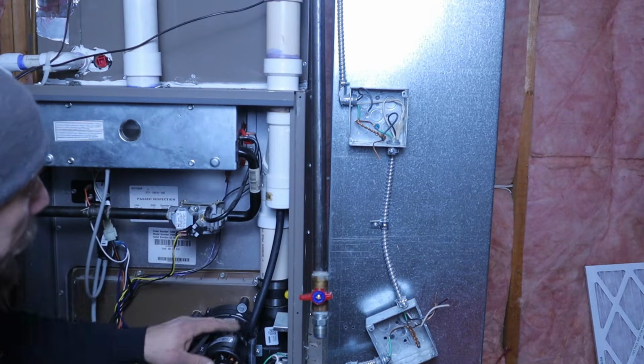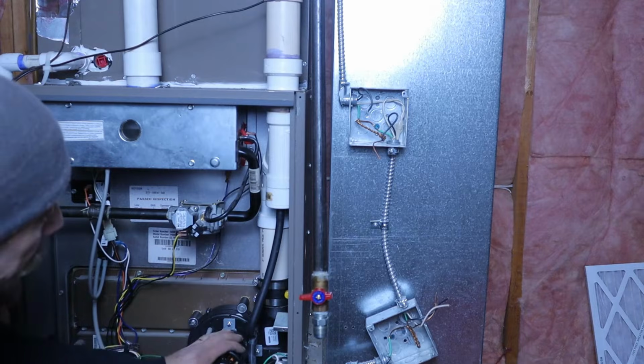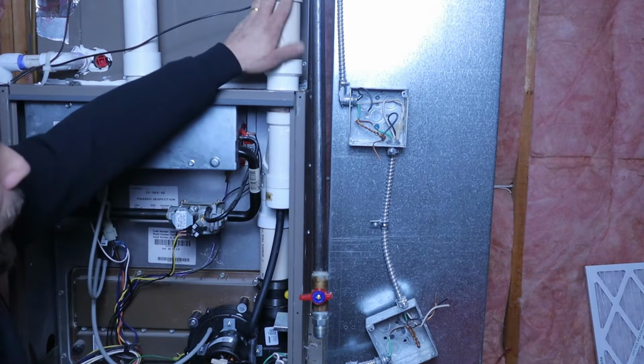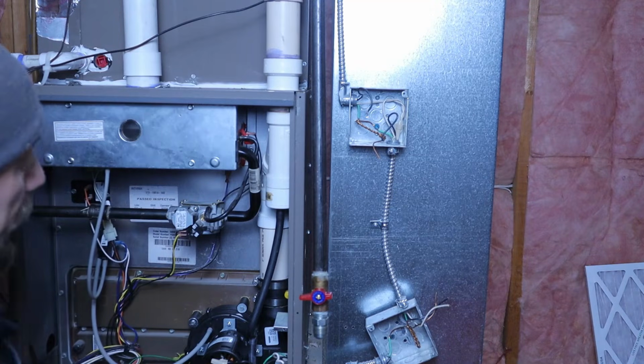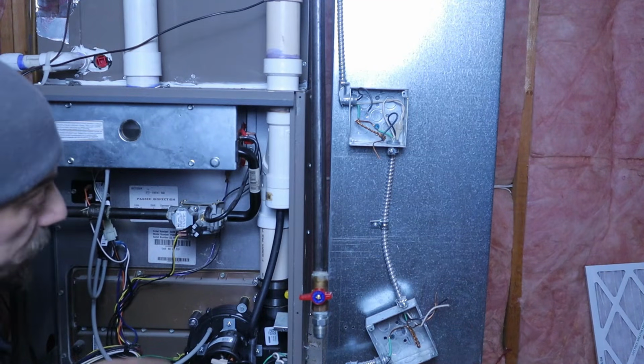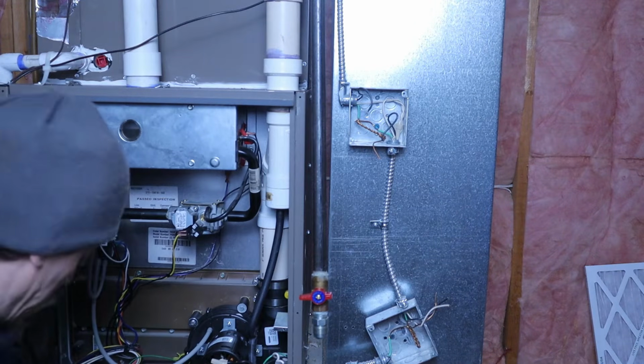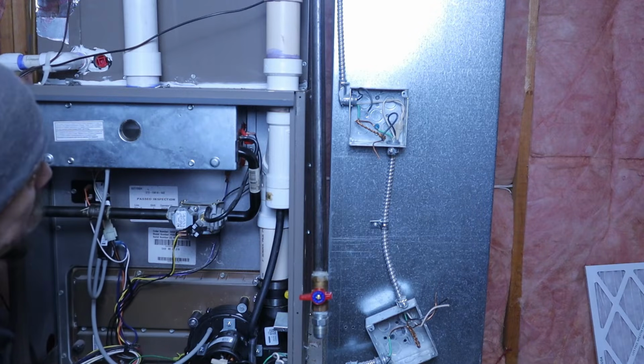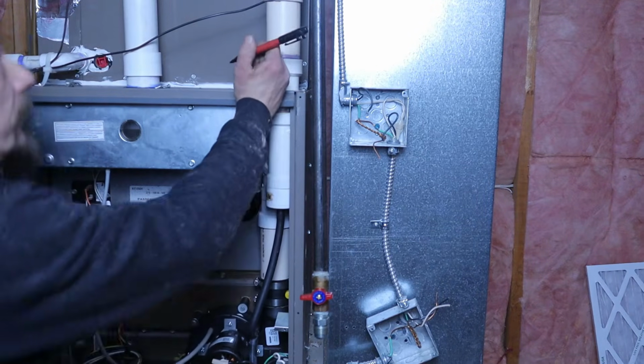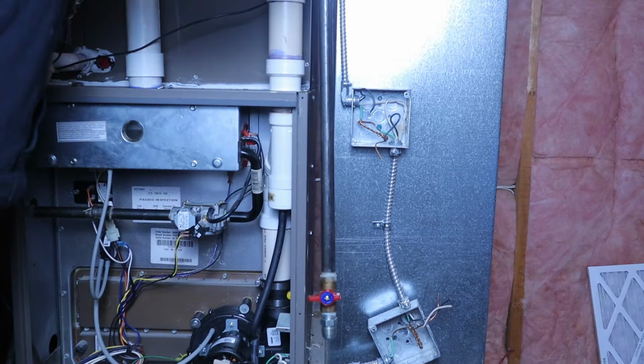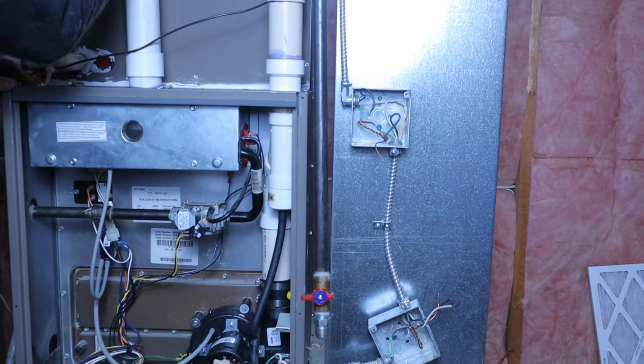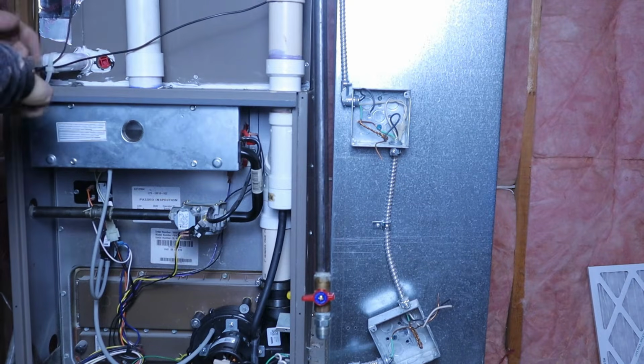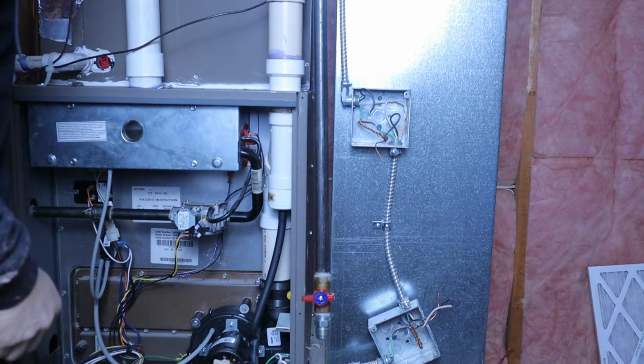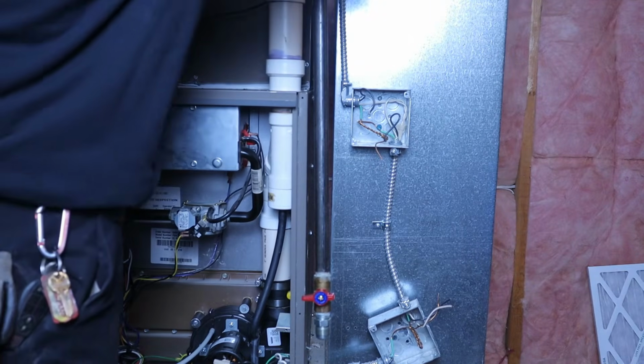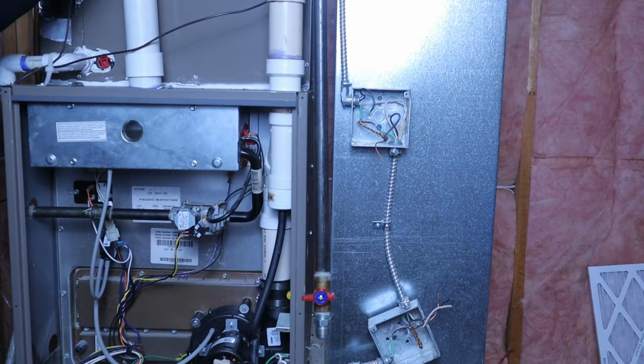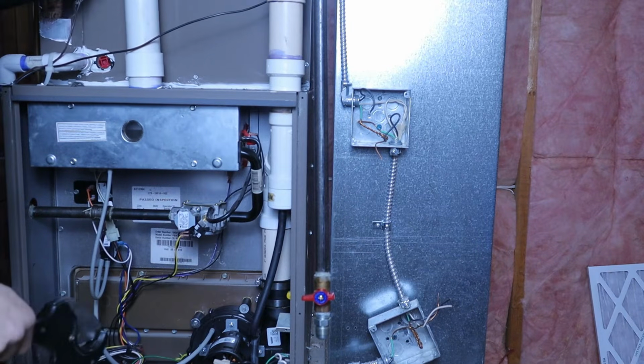So what I'm looking at here, Juan, is the inducer motor, you know that, right? And that's where our exhaust goes. So I know this is our exhaust pipe, so I'm gonna mark that off. A lot of times when you change these units out, as you know, they reverse, so we may have to, but this one I think we're good. So I'm gonna mark this as exhaust. And this is our fresh air intake. So I'll mark that. And now we'll cut it loose. There we go.